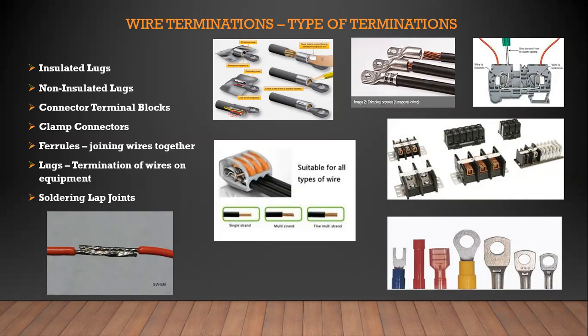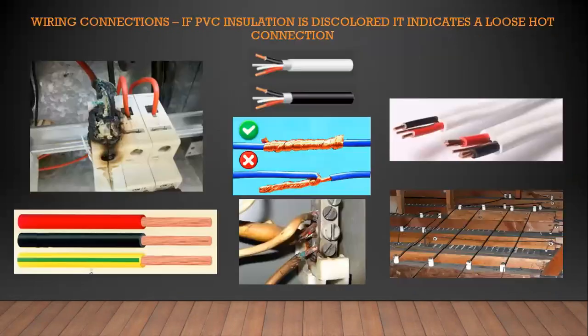Often we will see, 99% of the time, people haven't got the proper crimping tool to terminate the wires, and they just use pliers or a side cutter, and that will definitely create a loose connection over time and create fire hazards. Like you've seen on that slide, there was a loose connection. I've got some pictures in here, and what type of wiring, like I said, the surfix metal-sheathed cable, your twin and flat earth, or your conduit with your normal wires in.